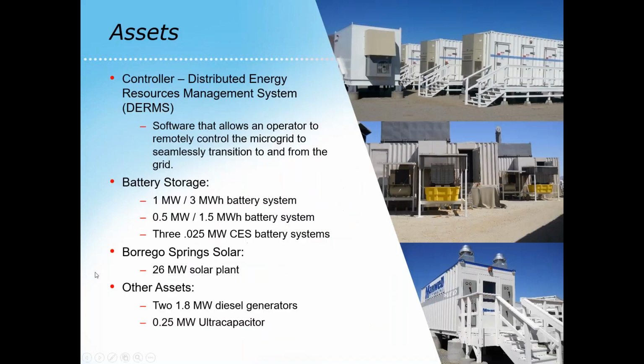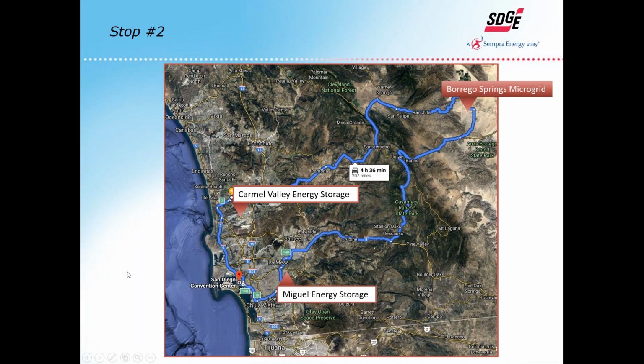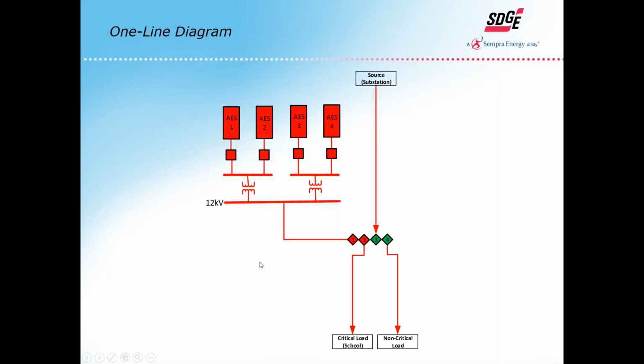It's actually connected through a 12 kV switch, which is a standard isolation switch we use for protective purposes on the SDG&E system. It's a standardized piece of equipment for us, but its ability to independently control isolating positions is why we use it as an interconnection device, since we already have a relay controlling this. So we just add in additional SDG&E logic to automate this system. That's also part of the reason we chose to connect at this site: familiarity, since our protection engineers and DER engineers already work with this device. So we're able to build it into our standard logic for interconnecting these battery and microgrid systems.